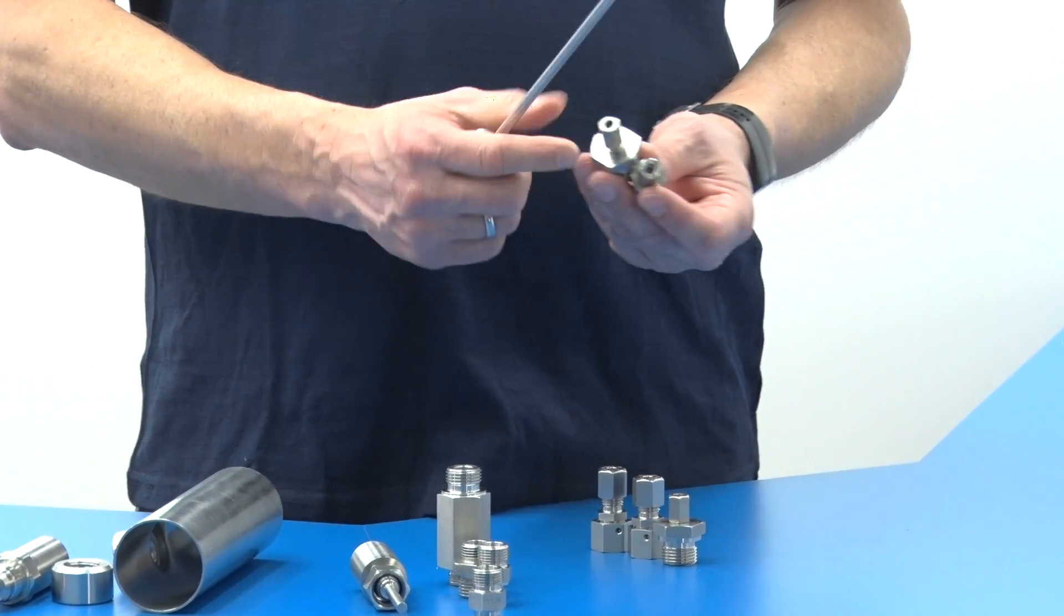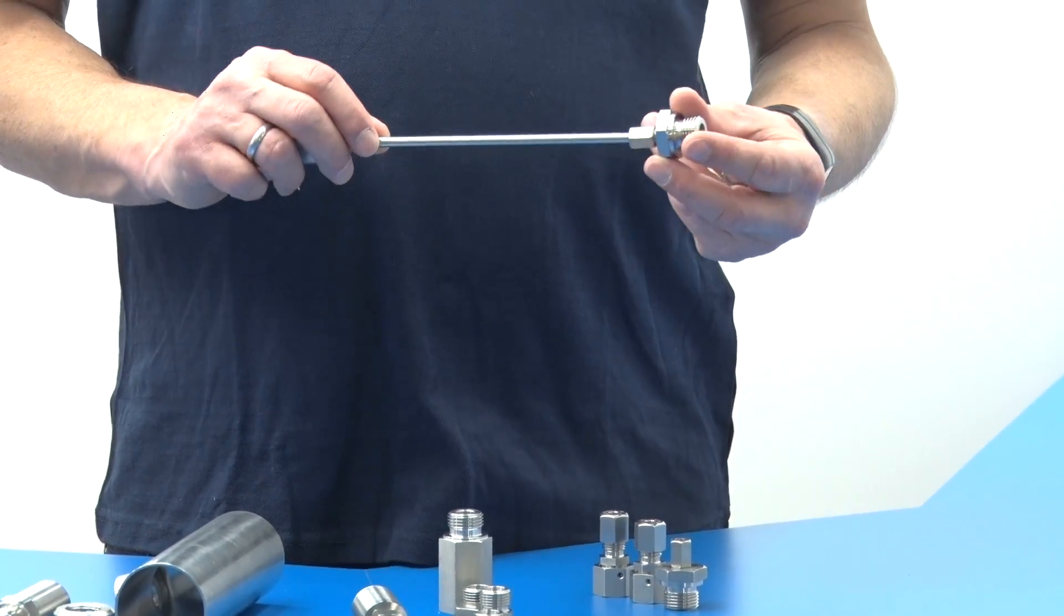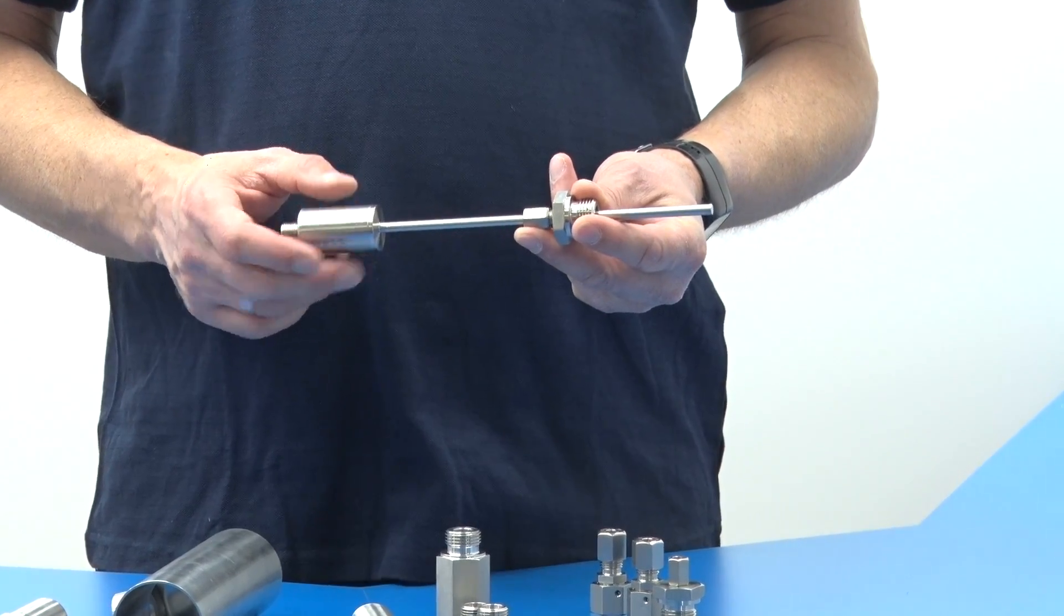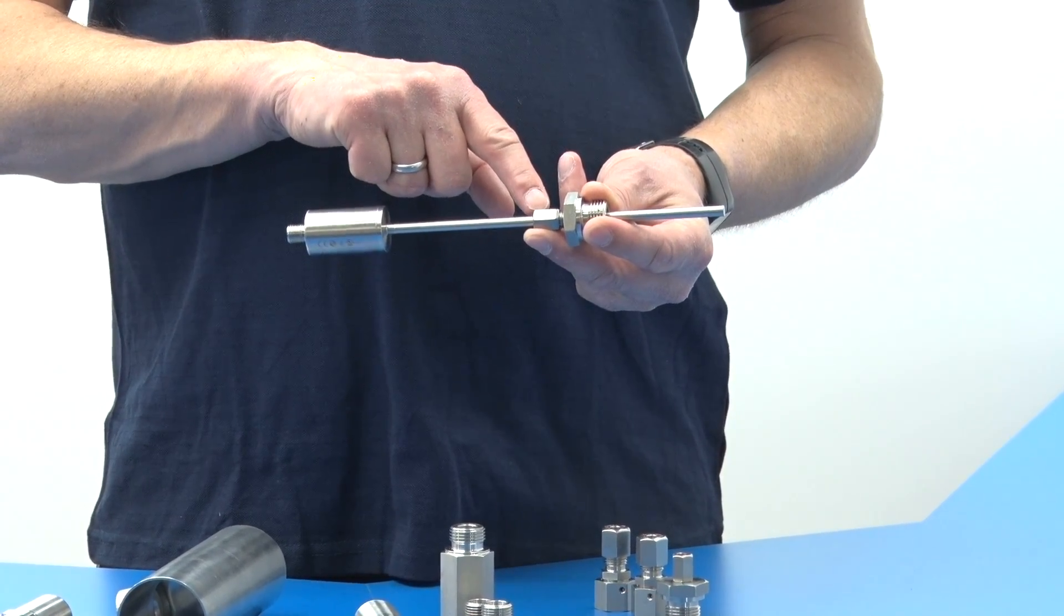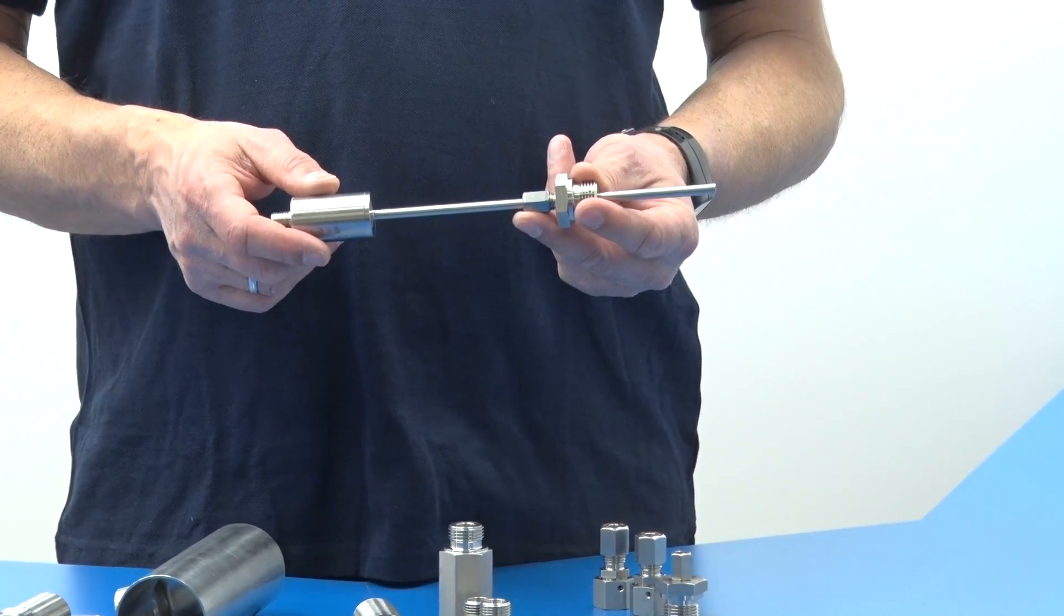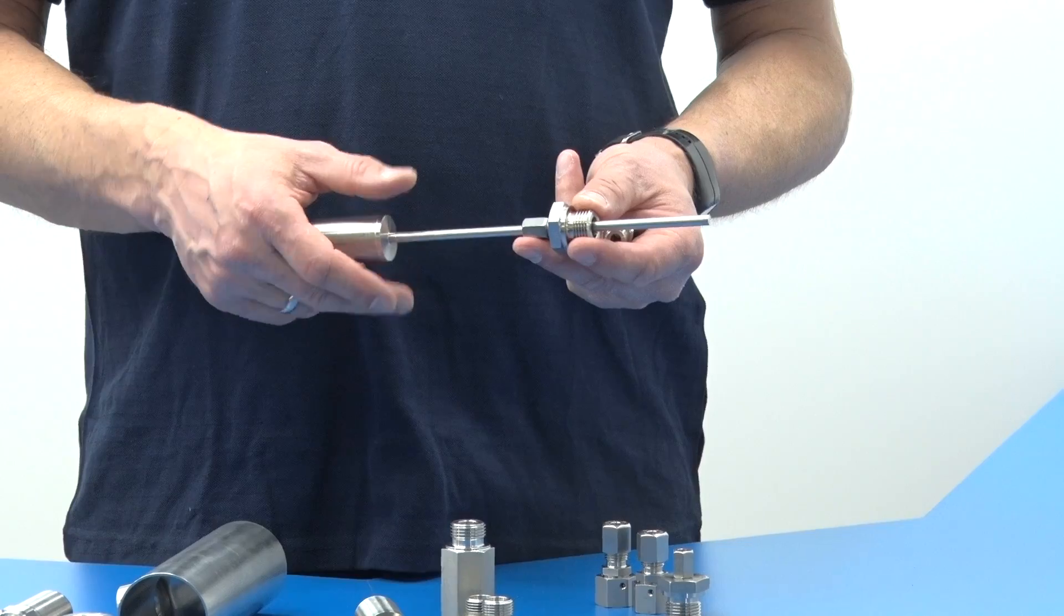Simply slide on the screw adapter, tighten it and the connection is safe up to 100-bar. However, bear in mind that sensor and adapter are permanently connected and cannot be separated. In high-pressure applications, this is the connection to choose.